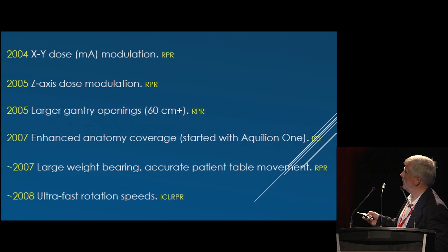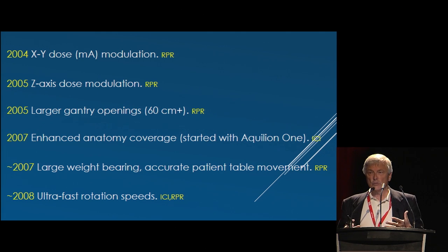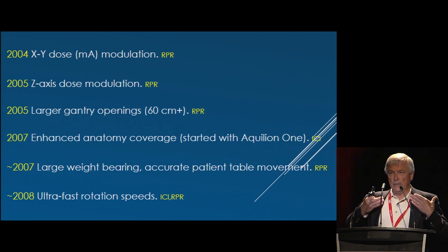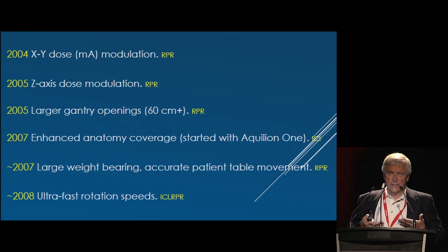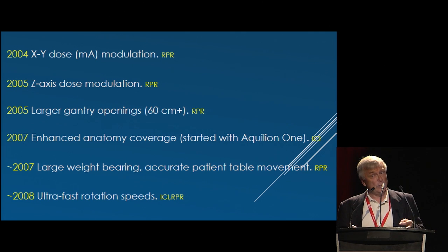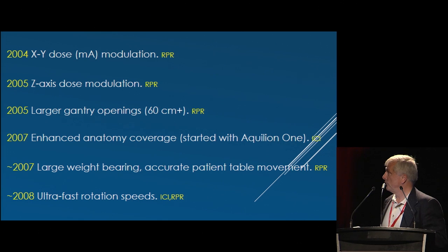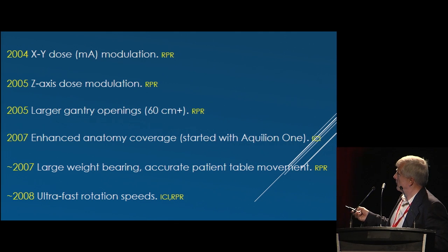In 2004, and right after that in 2005, we suddenly had dose modulation. So we realized that as we went through the chest cavity, we could reduce the MA, and as we went through the abdomen, we needed to increase the MA. That reduced the patient dose significantly, and people are starting to now really look at dose more than ever before. And so they did that in XY, and they did that in Z axis. Larger gantry opening started around that time too.